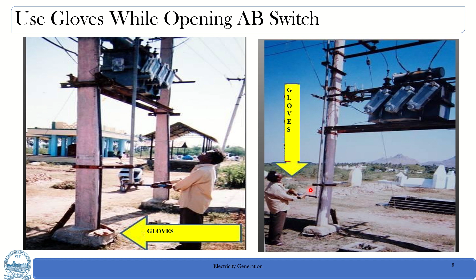See, in the first figure, the operator did not use gloves, simply using the iron rod to open or close the air breaker. This is an unsafe practice which you should not follow. And you can see in picture 2, he is wearing rubber gloves to operate the breaker. So this is the correct procedure. The hand-operated breaker switches should be effectively earthed by means of good wire, so that in case of insulation failure, there is an alternate path to the earth and the person operating is protected.